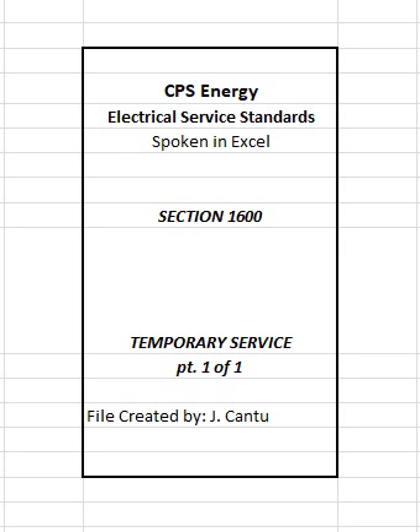4. Conduits shall be continuous from the connection at the customer metering enclosure to a point in the trench that is within 6 to 12 inches from CPS Energy's transformer or secondary enclosure, refer to Figure 1601. Exception. For residential use of temporary meter structures only, RMC, IMC, or Schedule 80 PVC conduits may be run above ground where not crossing property lines, not over 10 feet, and not subjected to physical damage or vehicular traffic including construction-related equipment. Conduits must be anchored sufficiently to prevent them from pulling away from transformer and temporary meter structure. CPS Energy shall make final determination on the conduits being subjected to physical damage.